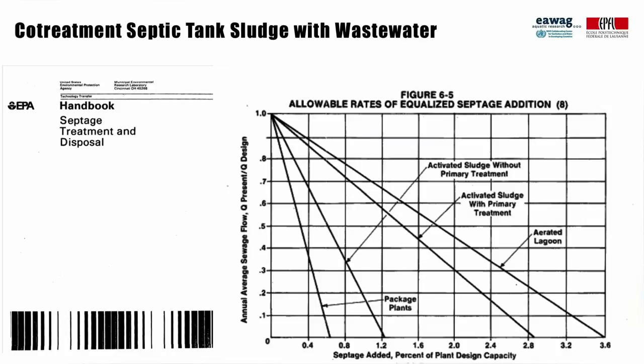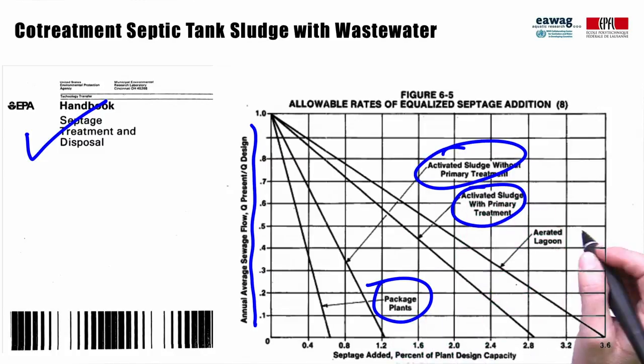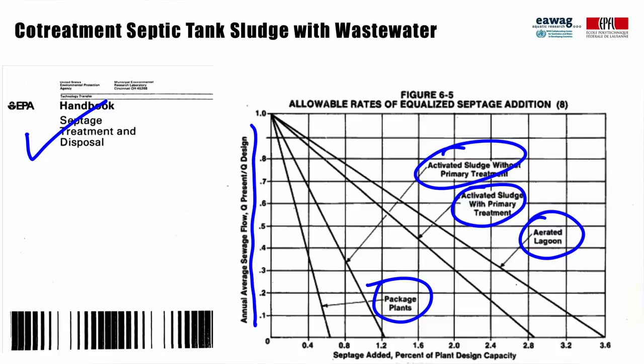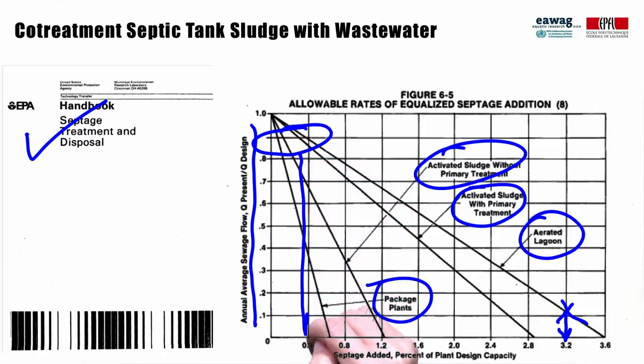This figure is from the 1984 US EPA publication on how to co-treat septic sludge in wastewater treatment plants. The allowed loading depends on whether the treatment plant is at capacity and what type of treatment technologies are employed. At only 10% of operational capacity with an aerated lagoon, you can still only add 3% of the total volume as septic tank sludge. For treatment plants operating at 90% of their capacity, the allowed loading volumetrically is less than one-half of 1% of the total influent volume.